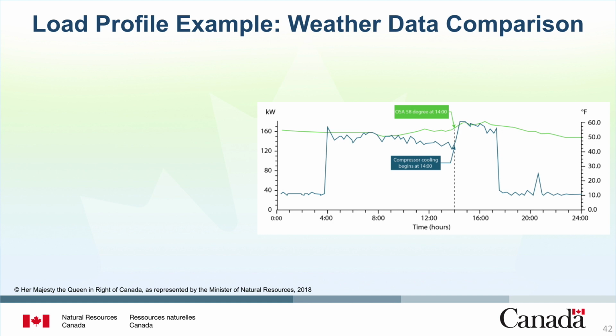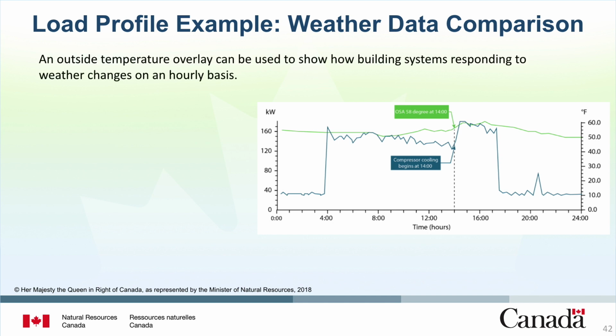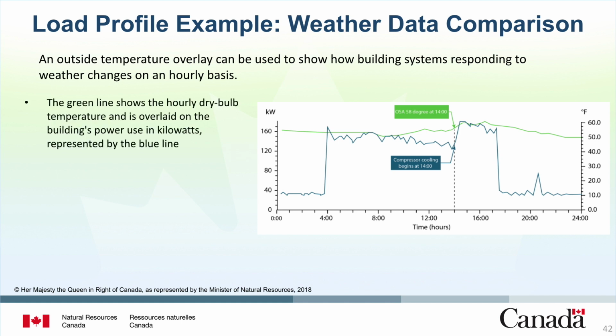The next example illustrates how a load profile can be used to assess how a building's systems can respond to weather changes. An outside temperature overlay can be used to show how building systems respond to weather changes on an hourly basis. The green line shows the hourly dry bulb temperature and is overlaid on the building's power use in kilowatts, represented by the blue line. This comparison can be used to determine if the HVAC economizer cycle is functioning.